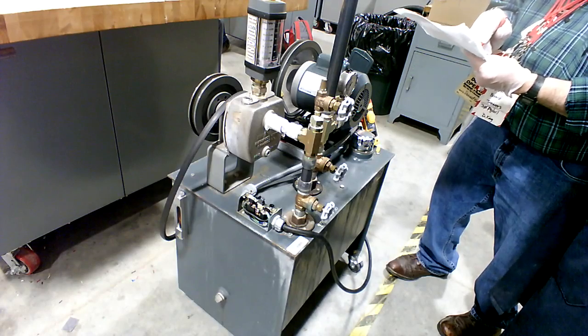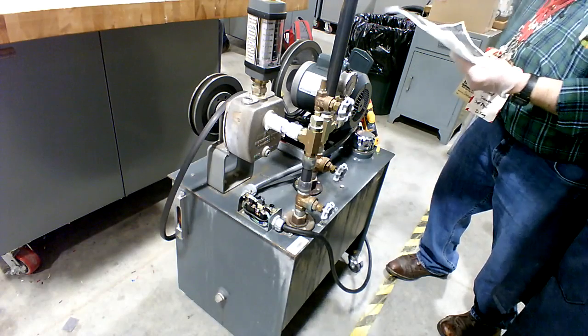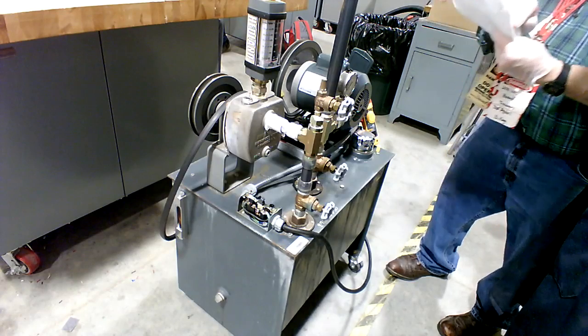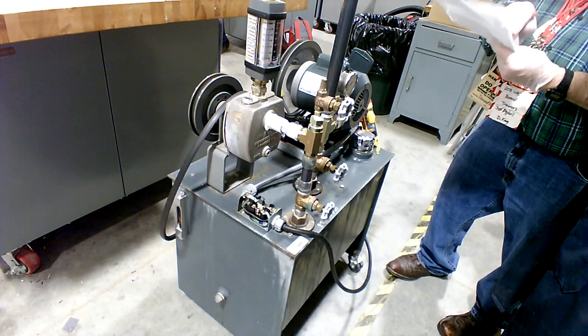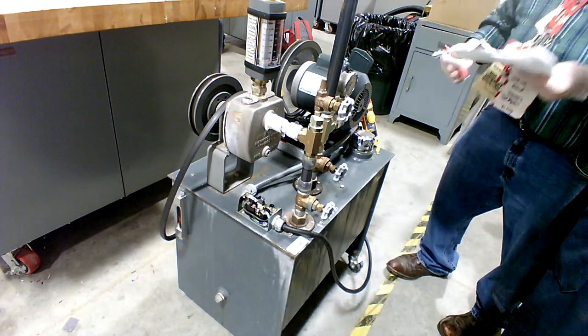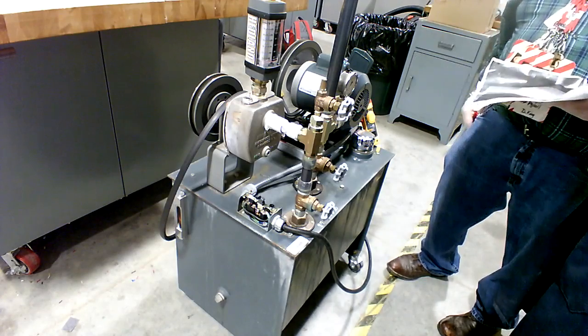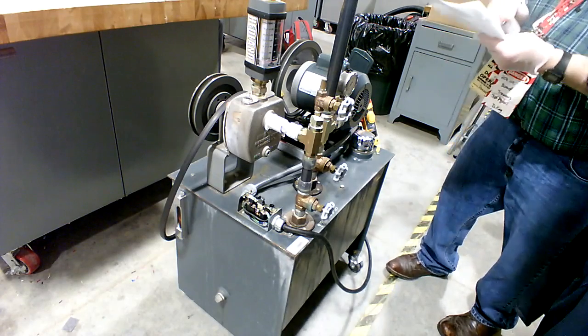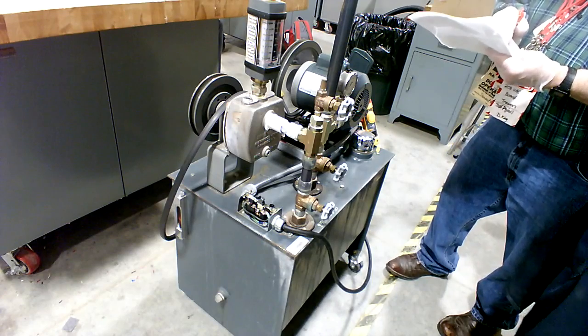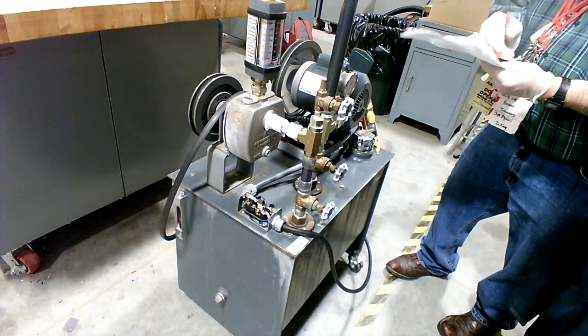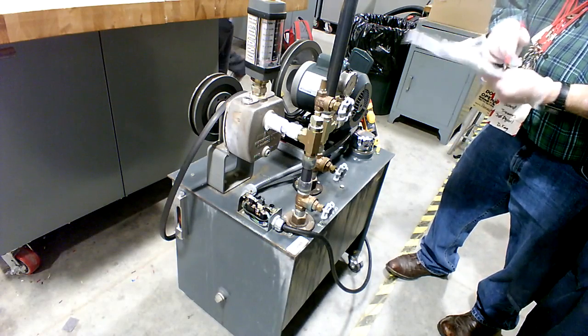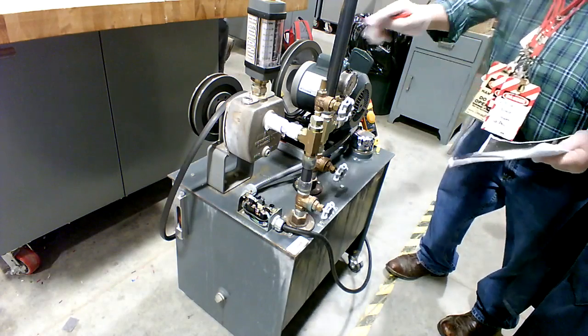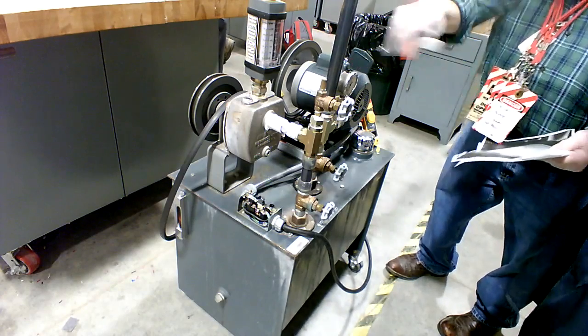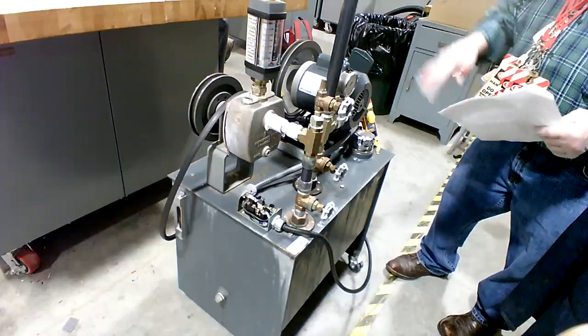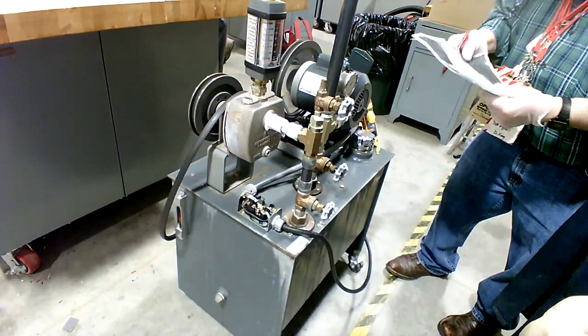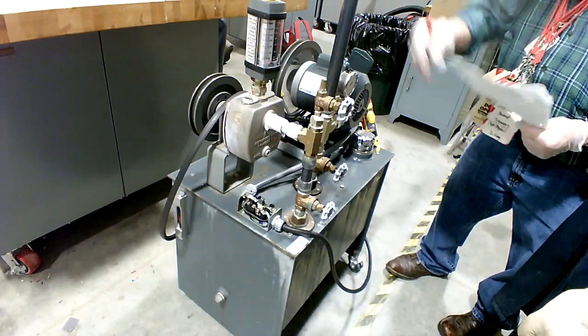If you're running on 230 volts, on the high voltage like over there, it would draw half that in amps. If you double the voltage, then the amps go down by half. You're running over here, so it's going to be somewhere in the range of 8.6. If the belt was hooked up, we could drive it. And there's no load on it right now, other than just the motor itself.